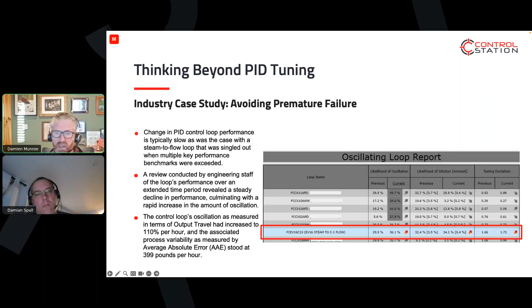Next slide: once you know there's an oscillation or a high average absolute error, you can then do something about it. You ask, what's causing the oscillation? What's the problem we have here? If you look at other metrics, you can see output travel was high - we were moving a lot. Output travel is the amount of movement the valve, the output, makes. It's a function or reflection of oscillation and average absolute error because the process has changed.